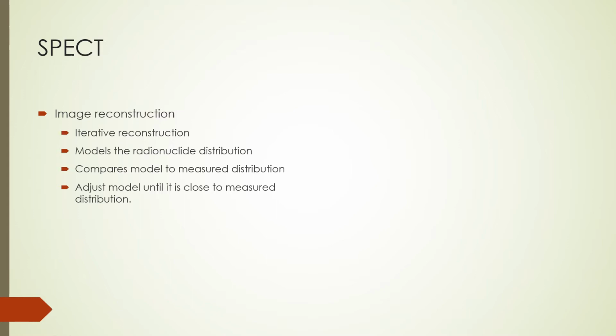mathematical model. The model takes into account the imaging characteristics of the scintillation detector and the patient attenuation characteristics if available. The calculated projections are compared with measured projections and adjustments made.